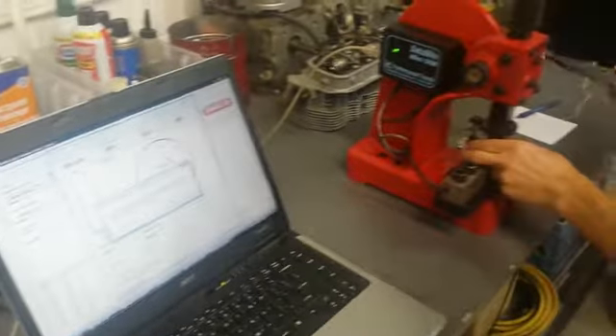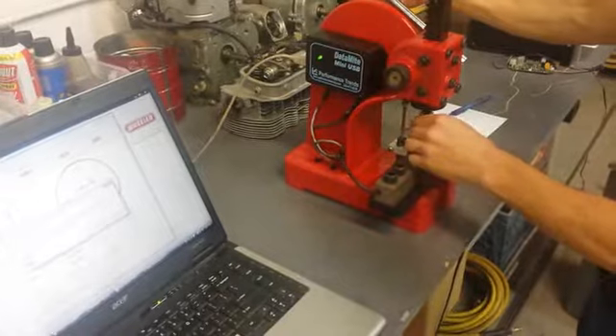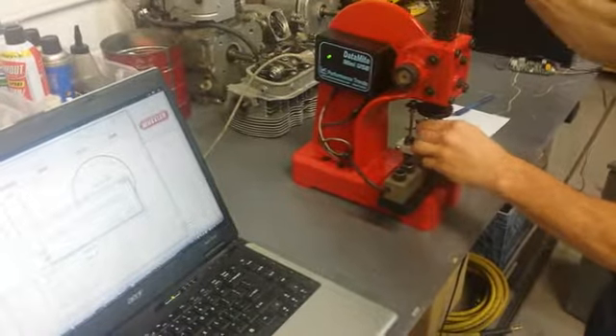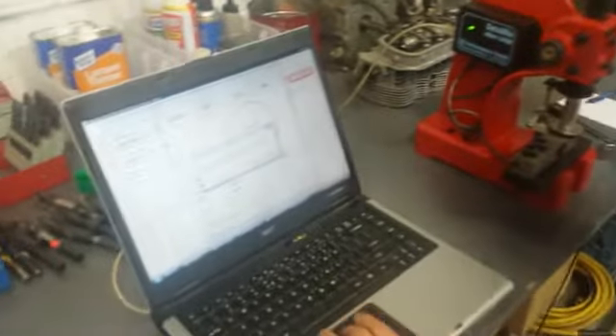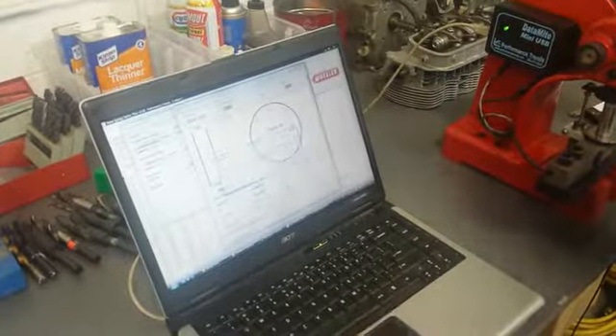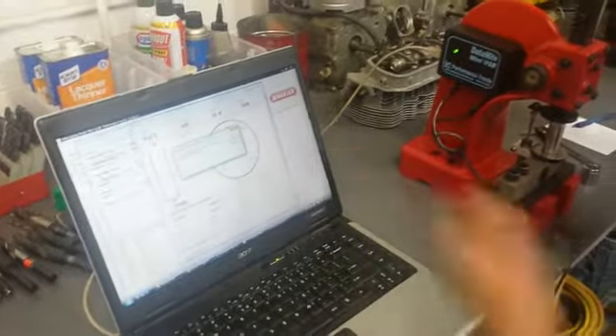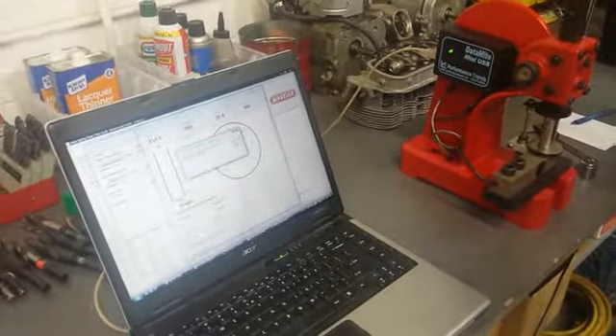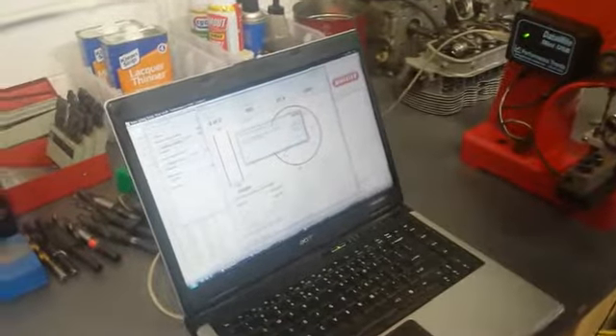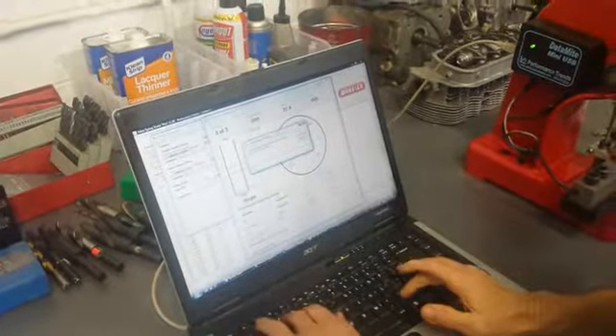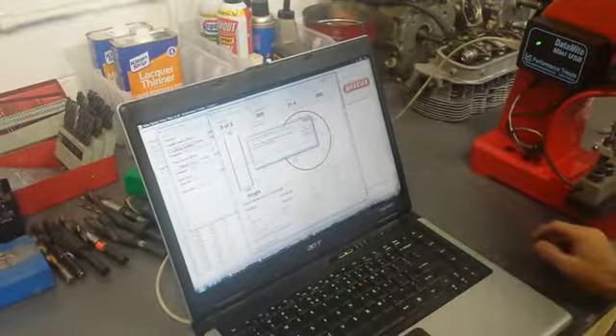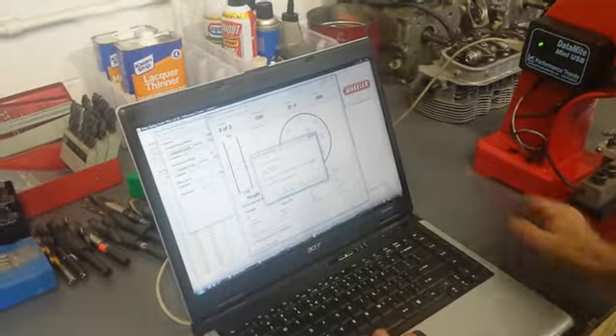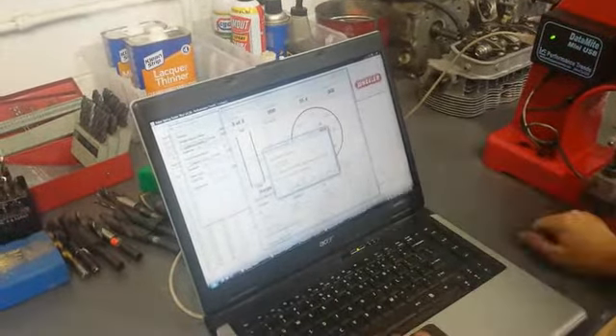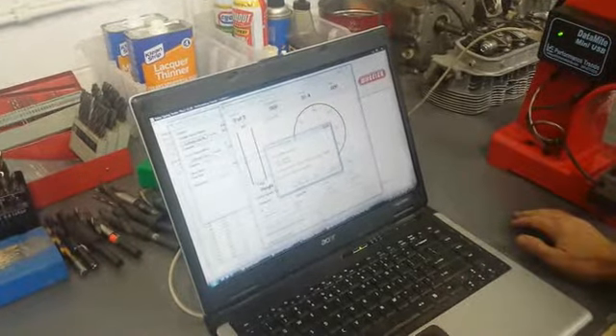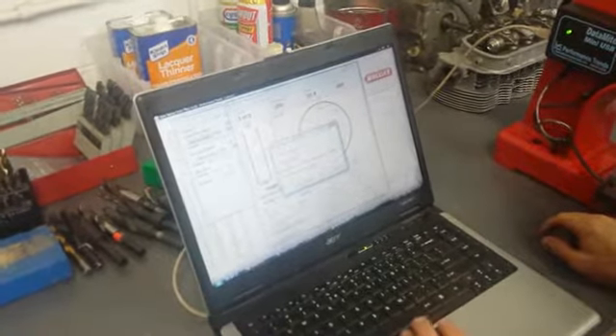Okay, then it says set a higher height. Okay, I'm going to set a higher height. And it took the readings and it says, what is that higher height? And that's 2.346. Okay. It's going to give us a little summary of what the two heights, what voltages it is, or in this case it's counts, and what the calibration numbers would be. It says, do you want to keep it?